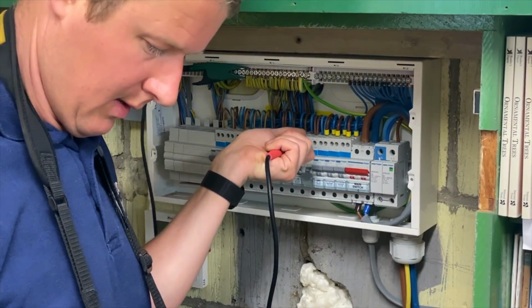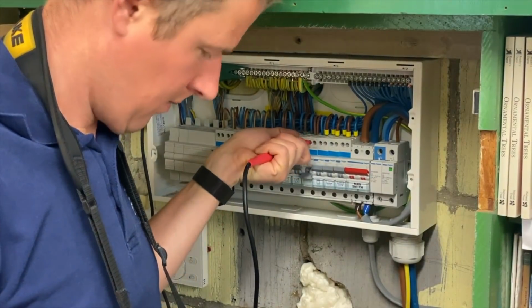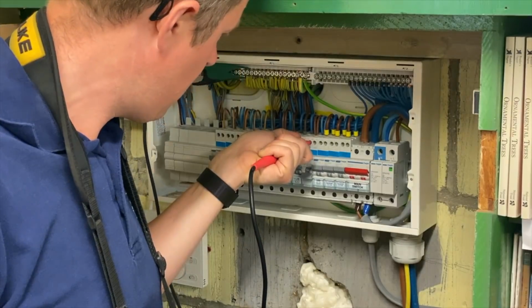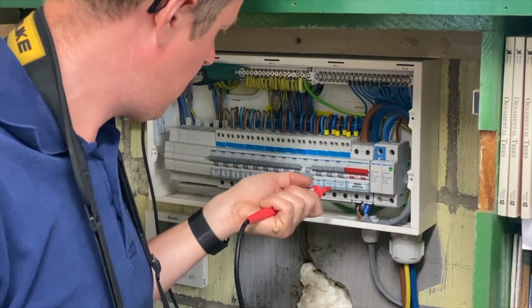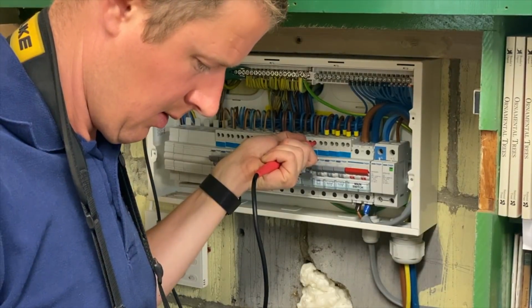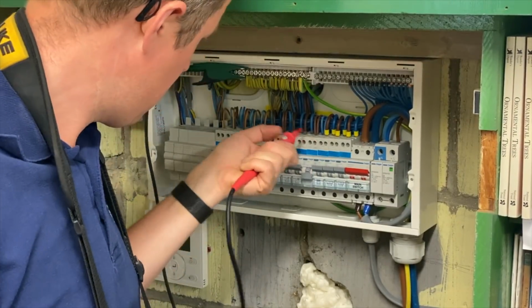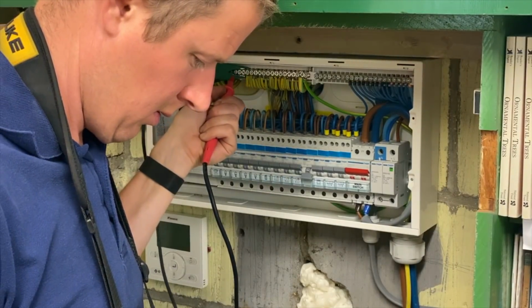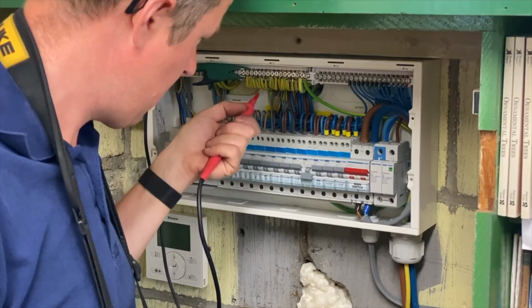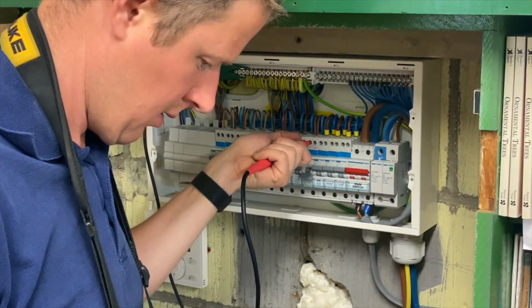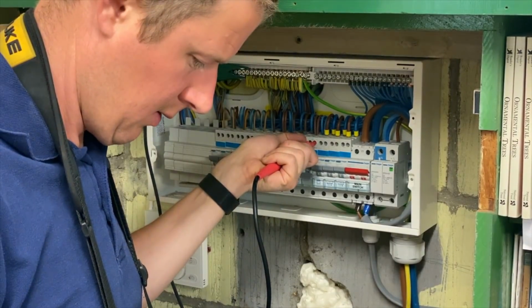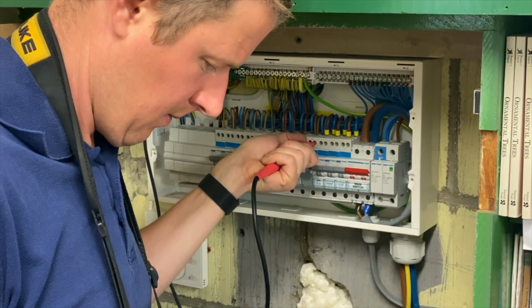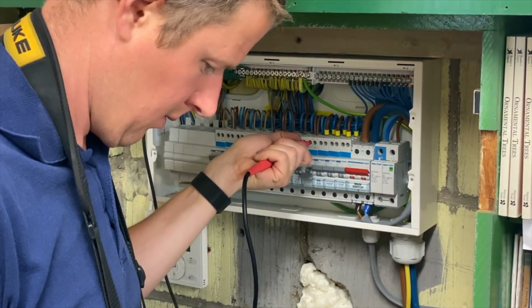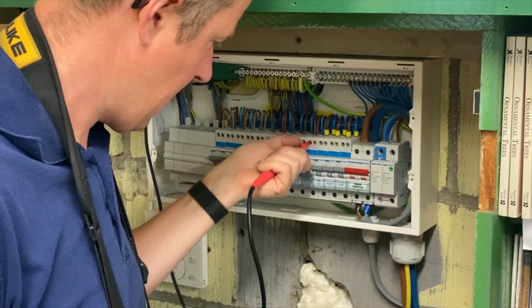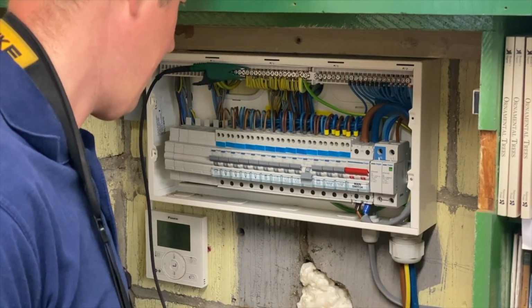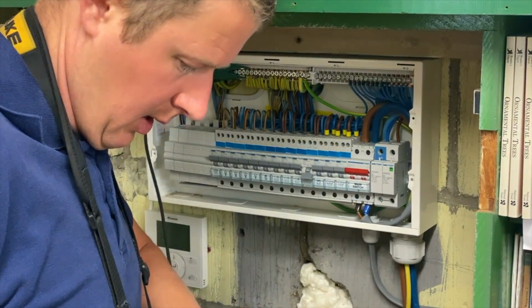Let me just do insulation resistance on here again, just to see what we've got. What? I've got 0 now. That makes no sense. I've got 0 megohms live to earth and 0 megohms live to neutral. How is that possible? Completely 0 and 60 ohms. It's not possible. It would go bang if that was the case. Oh man, I don't get this.